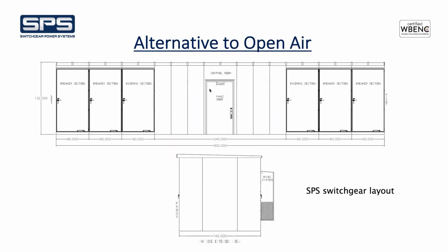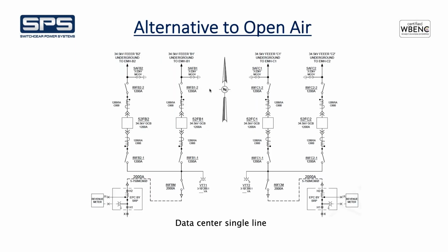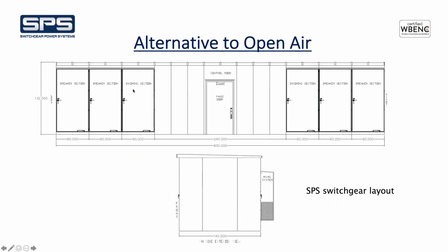And so this is the switchgear layout that we are providing. If I go back to the single line, you have your two breakers on each side, and then the incoming disconnect switch. So that is what you're seeing here, two breakers, incoming disconnect switch. So we're actually able to integrate the line and load disconnects for the breaker into the same section. And then one thing I will get into in a couple slides is the hybrid nature of this design, in that it includes non-walk-in switchgear and also an integrated control house in the same lineup. And that's why you see the HVAC right there.